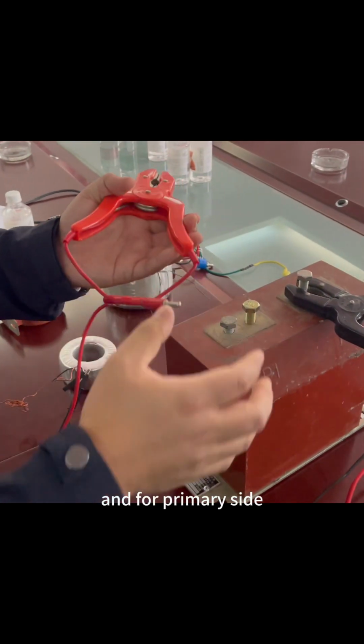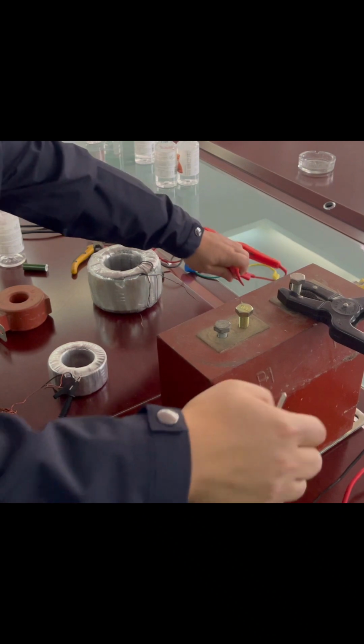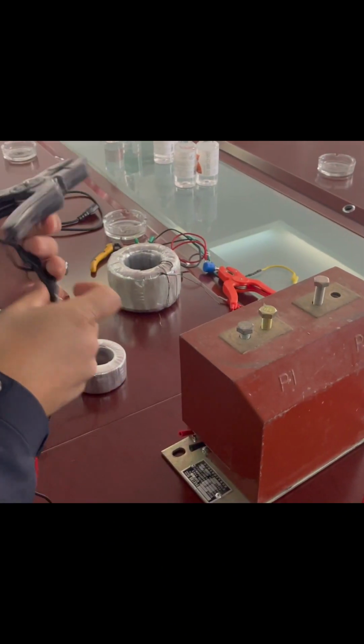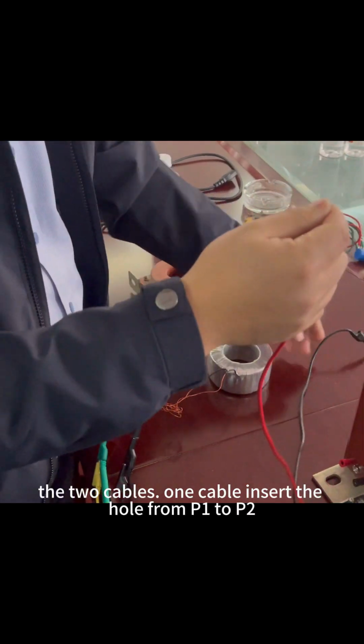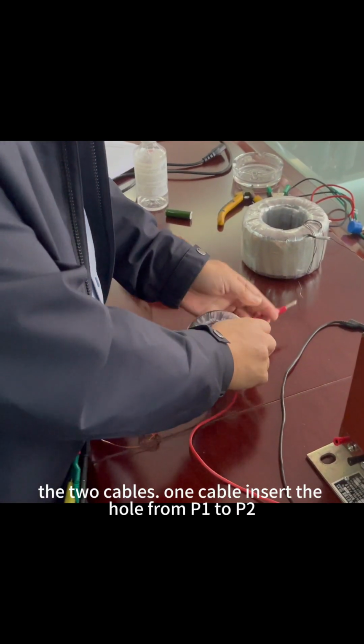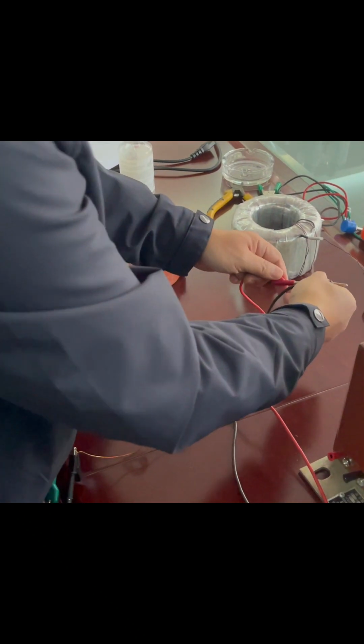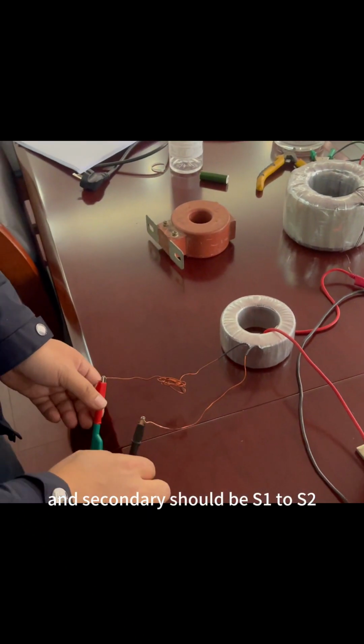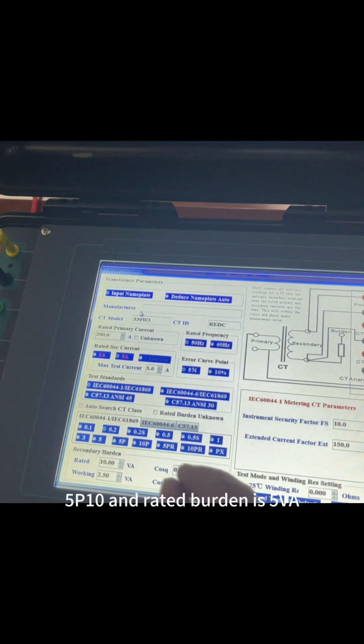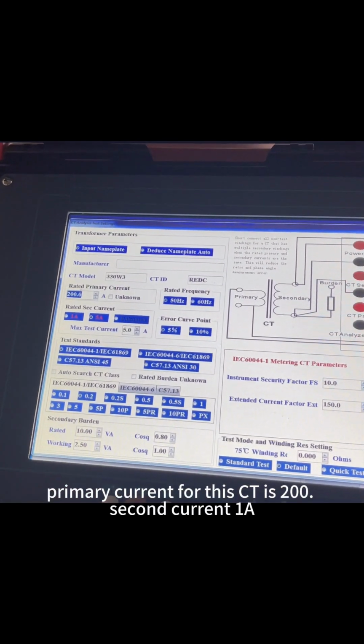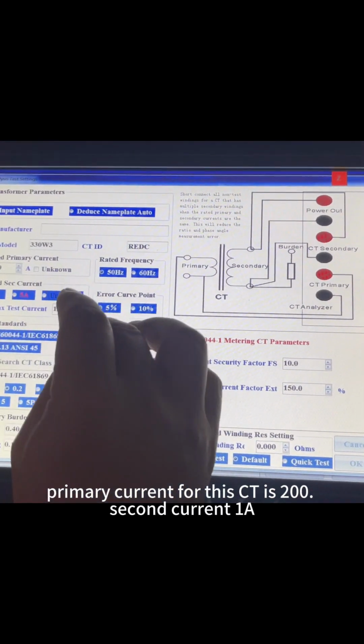And for the primary side, use two cables: one cable is inserted through the hole from P1 to P2, and the second goes from S1 to S2. For example, if this CT is 5P10 and the rated burden is 5VA, the primary current for this CT is 200 and the secondary current is 1 ampere.